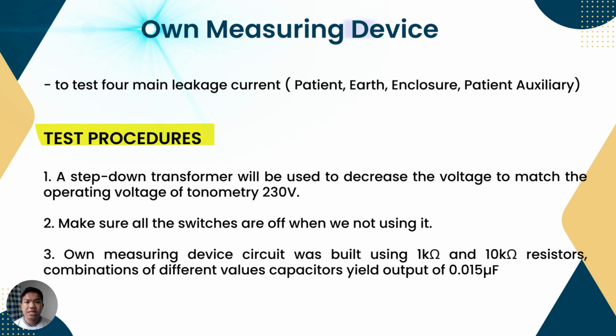The measuring device is to test the four main leakage currents, which are the patient leakage current, earth leakage current, enclosure leakage current, and also patient auxiliary leakage current. So what are the test procedures?